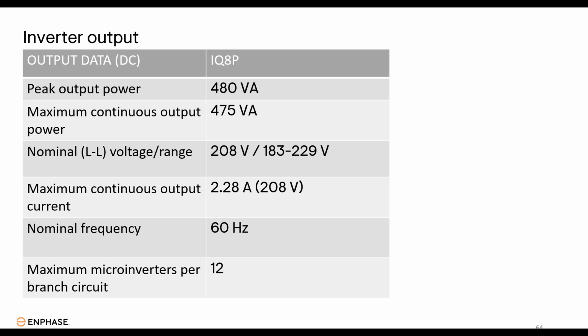Having that maximum number 12 makes it easier for designing, because all you have to do is take the total number of panels on your project and divide by 12. That's how many circuits you're going to have. Now, if your project doesn't have a perfect multiple of 12, then you're going to want to have as many circuits as possible fully loaded with 12, and then try to keep the other circuits in multiples of 3, 6, 9. That way we get better phase balancing across each circuit.